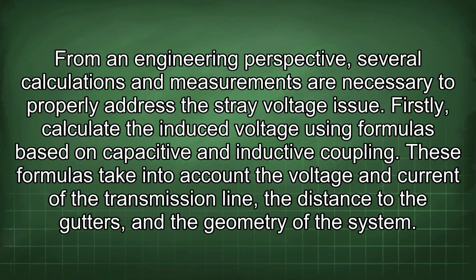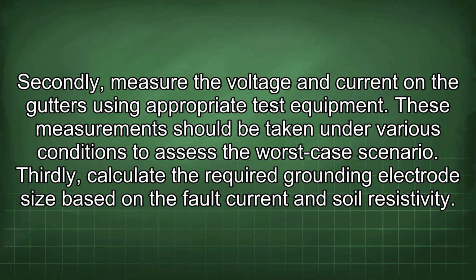From an engineering perspective, several calculations and measurements are necessary to properly address the stray voltage issue. Firstly, calculate the induced voltage using formulas based on capacitive and inductive coupling. These formulas take into account the voltage and current of the transmission line, the distance to the gutters, and the geometry of the system. Secondly, measure the voltage and current on the gutters using appropriate test equipment. These measurements should be taken under various conditions to assess the worst-case scenario.